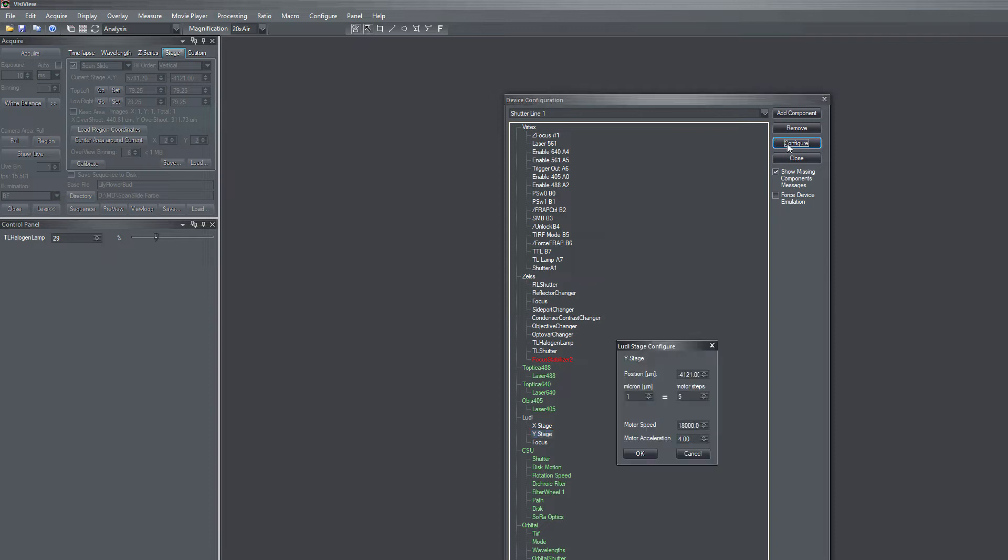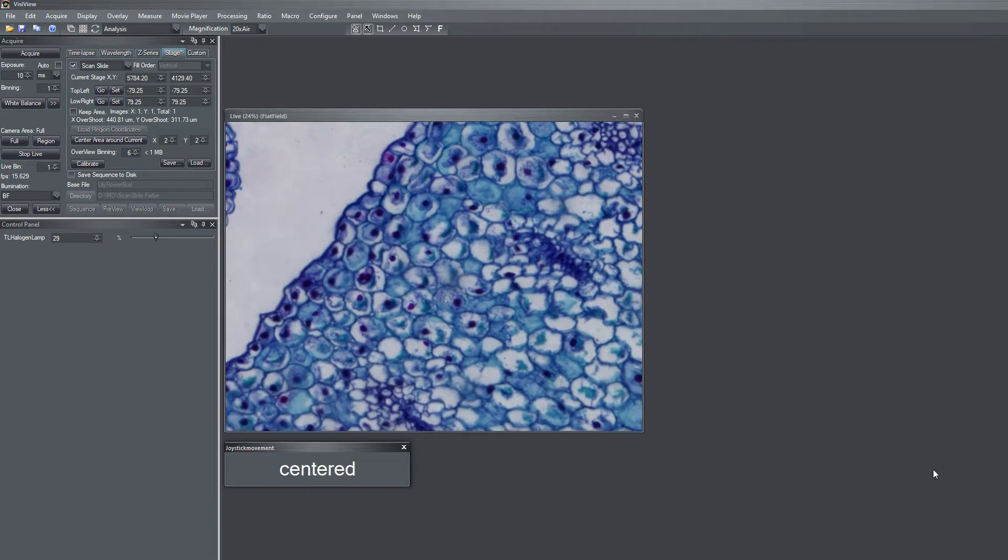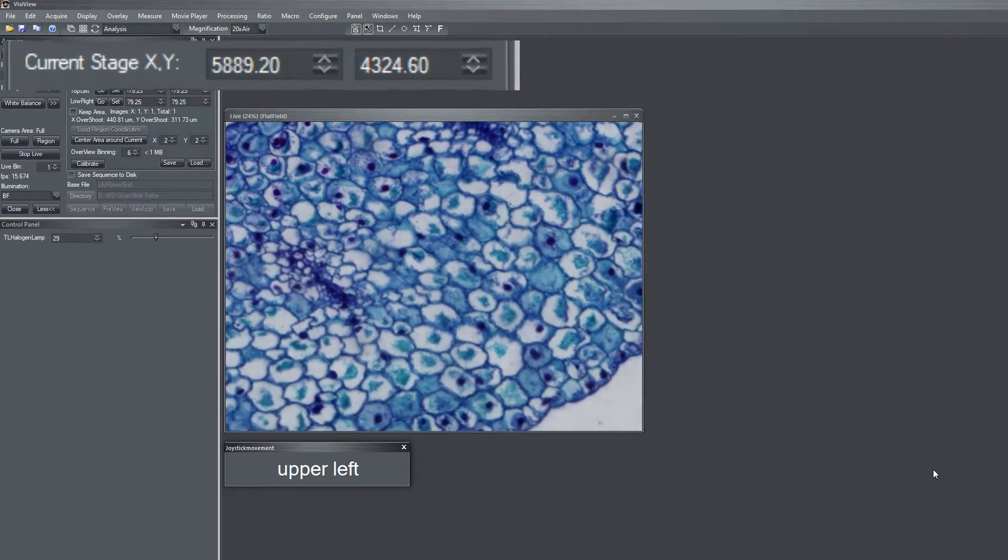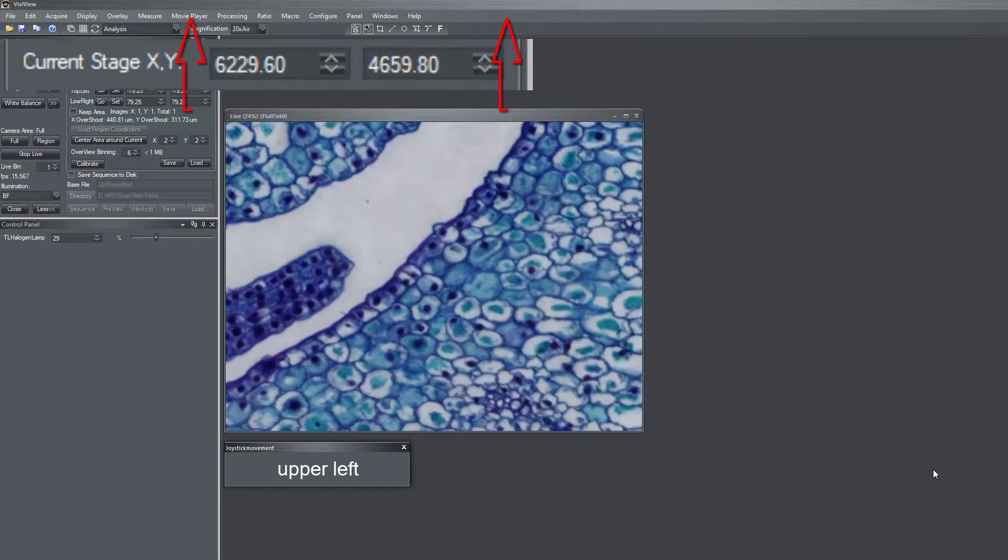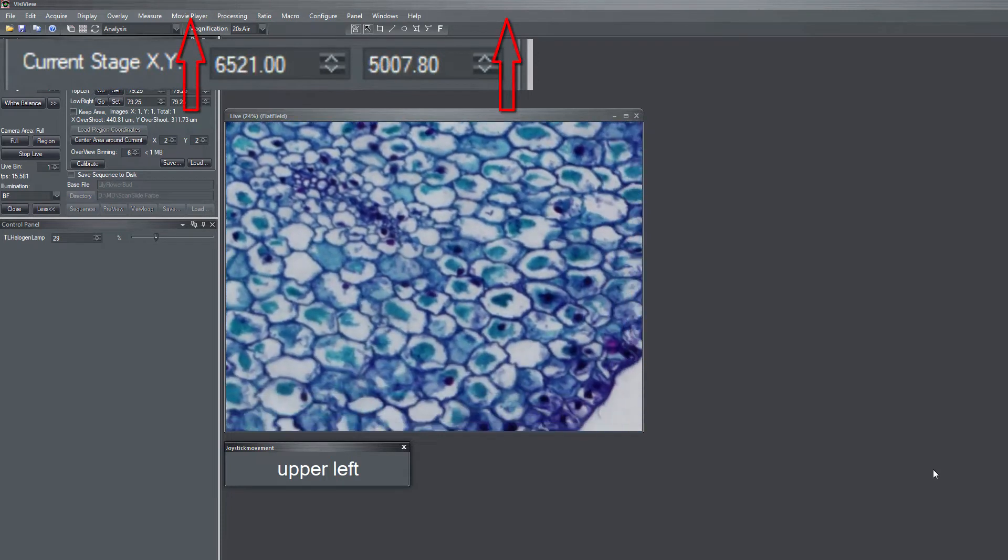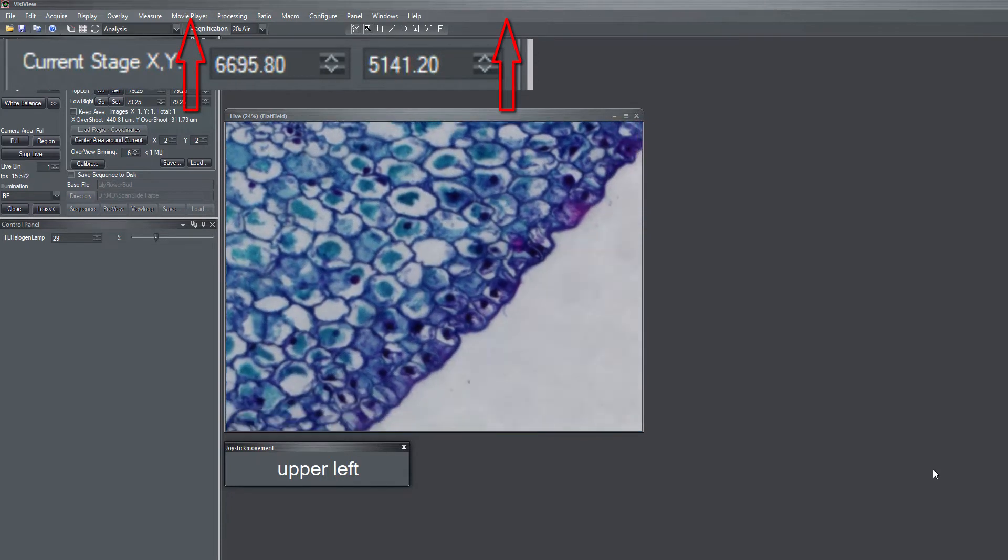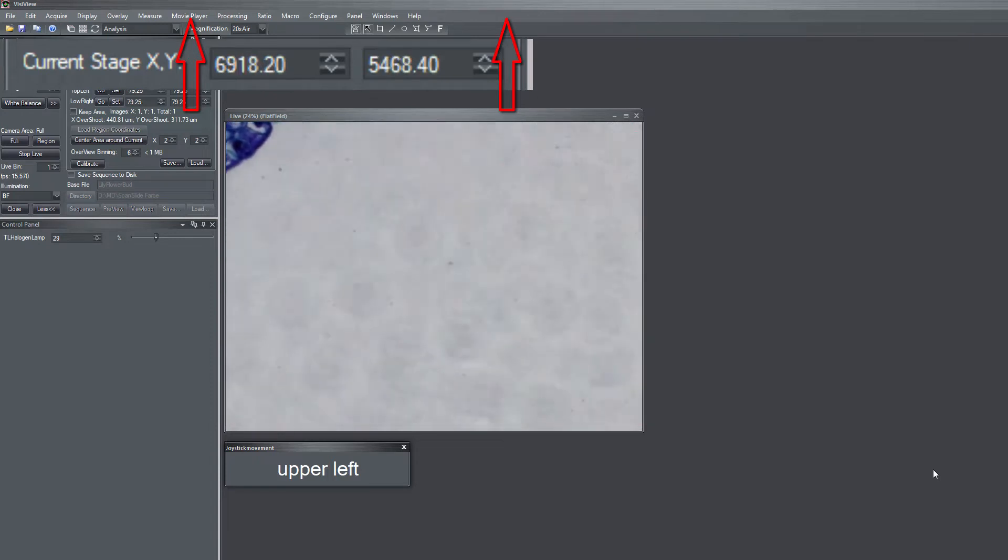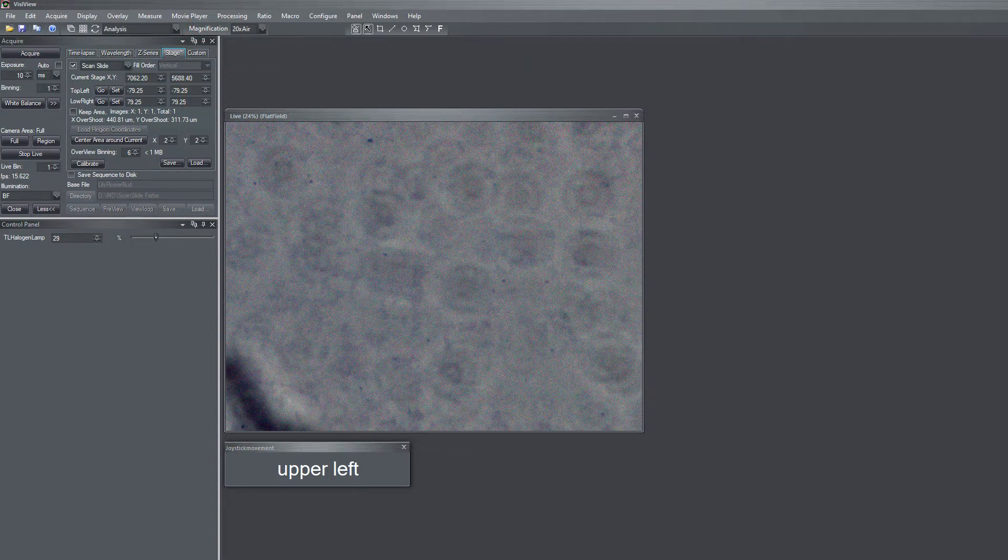First we have to stop the live and then we have to go to configure devices. In configure devices we find the y-stage. I click on configure and now we just simply change the polarity of the motor steps to minus 5. And now let's check again. If we move again the sample to the upper left, we see that now both the x and the y-axis values increase.